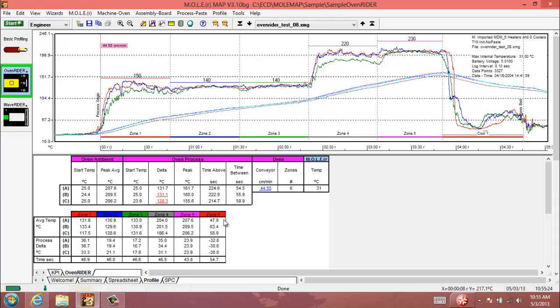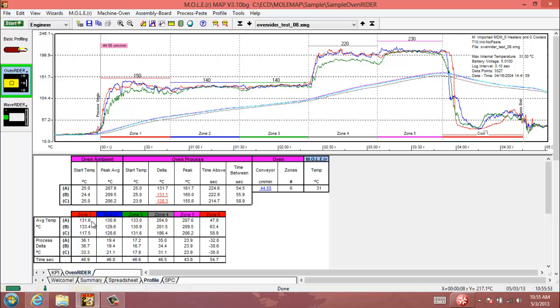Some of the really valuable information is in this lower table here, where the average temperature for each of the ambient sensors across the width of the palette are displayed. This is the ambient base average of the center 70% of each zone. We basically ignore or disregard the outside 15% on each side of a zone to get you the most accurate information as far as how that zone is heating your product.